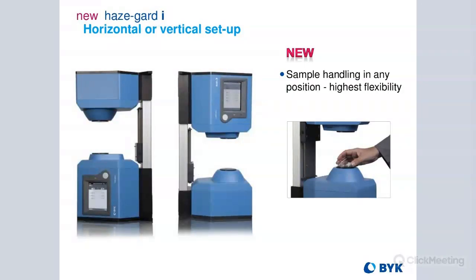With a vertical setup option: with the previous generation, our HazeGuard Pluses could only be oriented horizontally. This one can actually be oriented both ways — horizontally or vertically — and you can change back and forth. The benefit is that you could lay the sample down on the port instead of having to hold it in place vertically. This is particularly good when you have very small samples that are just a little bit bigger than the aperture port in the HazeGuard, so you can just sit the sample on the port instead of worrying about your fingers getting in the way of the light beam.